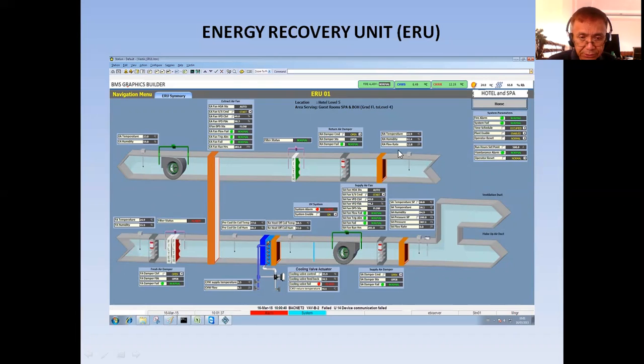Okay. Now the heat pipe is recovering the energy coming from the return air. Then this heat pipe is just a pipe like a cooling coil, but instead of chilled water, it contains refrigerant wherein the refrigerant just keeps on circulating in this heat pipe. So it recovers the energy from the return air, then it pre-cools the outside air temperature, and likewise the same concept with the wraparound heat pipe in the cooling coil. Okay, so this is the only difference of this air handling unit from an ordinary one. As the name implies, energy recovery. So it's just trying to recover the energy from the return air because that return air is still cold. So it's being used here in this heat pipe.